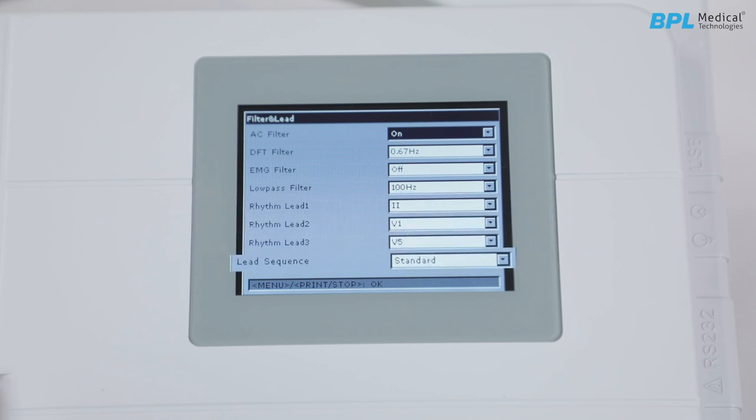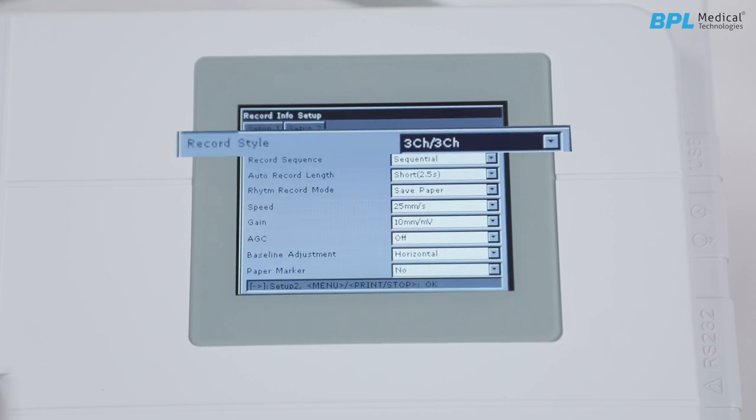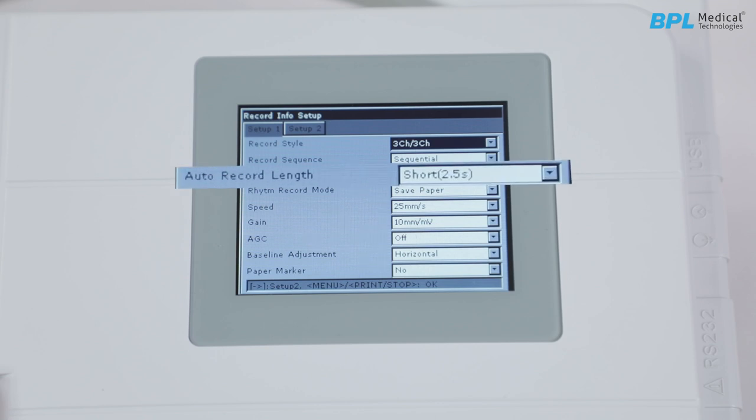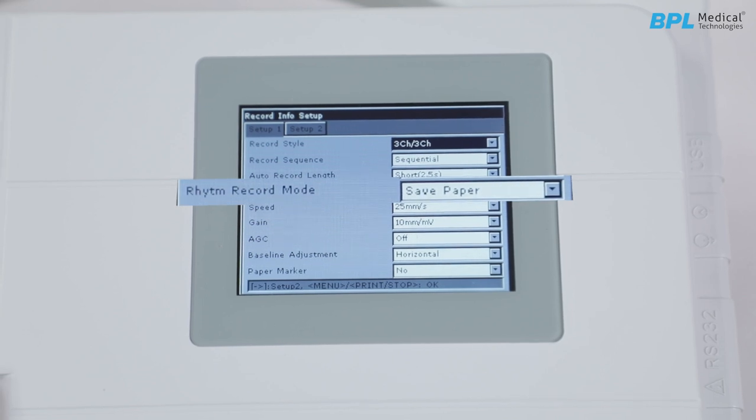Next is the record info setup. Record style sets the print format required for the printout. Then we have record sequence — whether the lead needs to be printed sequential or synchronized. Next is the auto record length, then a rhythm record mode. Save paper prints after sampling 10-second ECG on a single paper; Quick prints immediately but in a detailed layout.